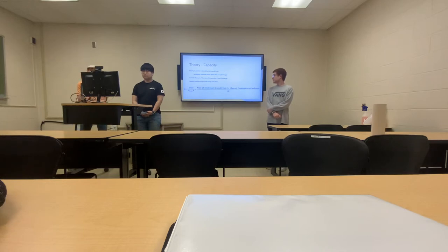But theoretically, it also comes from the UA delta T over delta H evap, which means that when you're actually operating things, what we don't know on this system is what the U number is on that equation. So that's one of the things you'll identify in the lab. But that can change over time as you operate in a real system, because you can have fouling, which will change the thermal conductivity of the system.